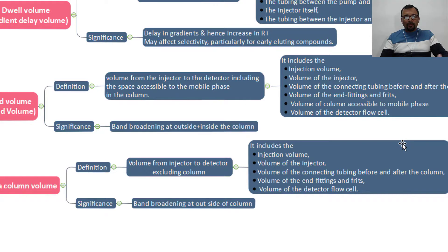The components that account for extra column volume are: injection volume, volume of the injector, volume of the connecting tubing before and after the column, volume of the end fittings and frits, and volume of the detector flow cell. These are the three different terms explained, and each term has its own significance.